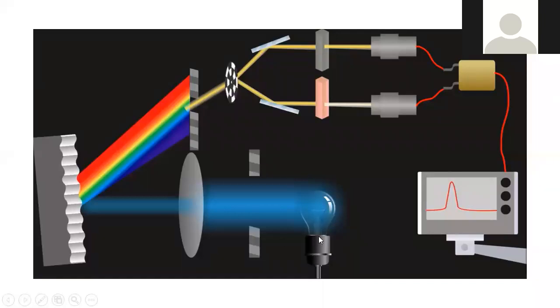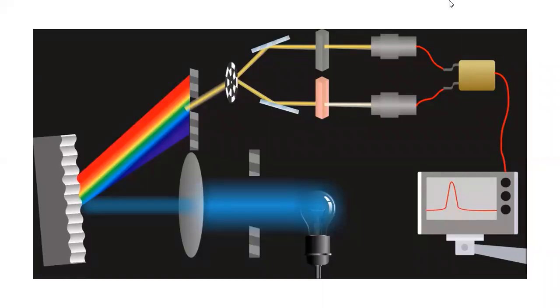First, we have the source of light. We use two types of lamps here — a combination of two lamps. First, the hydrogen-deuterium lamp, and second, the tungsten-filament lamp. Two lamps are used because this is UV-visible spectroscopy, meaning there are two radiation ranges here. One is UV and one is the visible range. The hydrogen-deuterium lamp covers all the UV region. If you have a UV radiation wavelength, you use the hydrogen-deuterium lamp. If you have the visible region, you use the tungsten-filament lamp. If you use both, then we use a combination of these two.